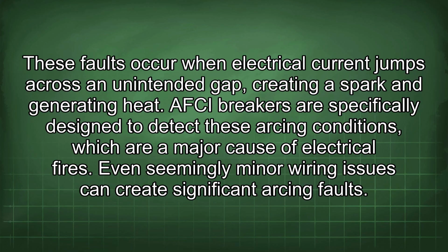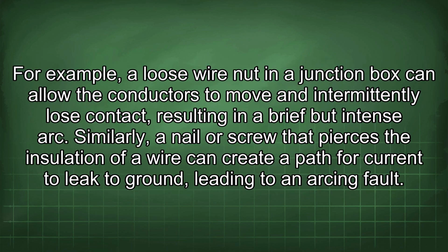AFCI breakers are specifically designed to detect these arcing conditions, which are a major cause of electrical fires. Even seemingly minor wiring issues can create significant arcing faults. For example, a loose wire nut in a junction box can allow the conductors to move and intermittently lose contact, resulting in a brief but intense arc. Similarly, a nail or screw that pierces the insulation of a wire can create a path for current to leak to ground, leading to an arcing fault.